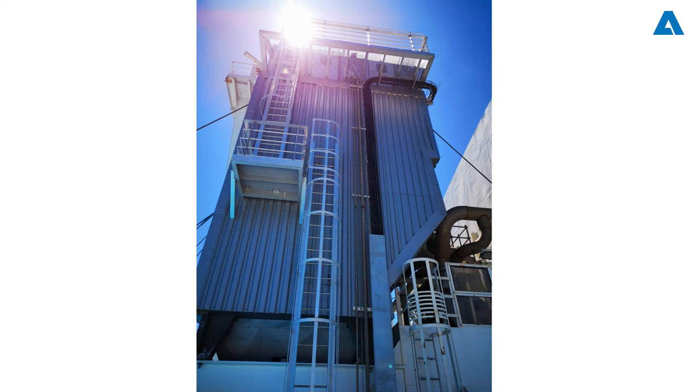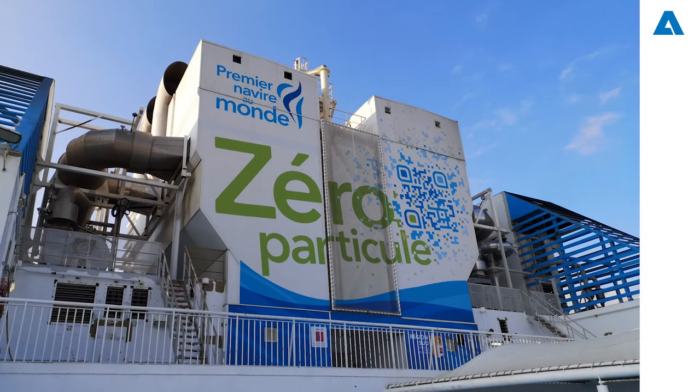An important part of our system is a fabric filter and the usage of bicarbonate powder as a sorbent. The reagent injection provides sulfur absorption while the filter bag technology retains all the reaction products together with the pollutant residues from the combustion process. For the removal of NOx, injection of urea solution and a catalyst is used. The multi-filtration system developed by Andritz removes SOx, NOx, and particulate matter simultaneously.